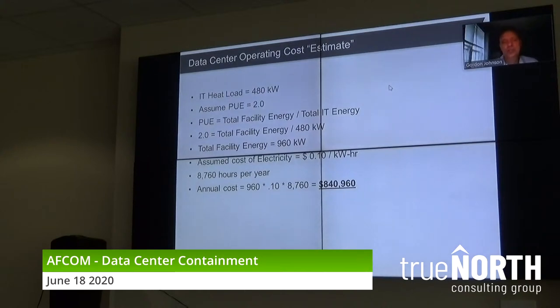Let's look at the cost estimate of this data center. And this math is very accurate because there's not much to it. So if you say, well, you know, does this work for my data center? I can guarantee it does. If you know your IT heat load, and everyone does, they can get that from their UPS units or their PDUs, but let's just say your heat load is 480 kW. Now, does everyone know their PUE? Not necessarily. But if you don't have containment, I'm going to guess that it's between 1.8 and 2.0. If you know that number, you have everything you need because you know how much you're spending on your electricity. You have an energy bill.